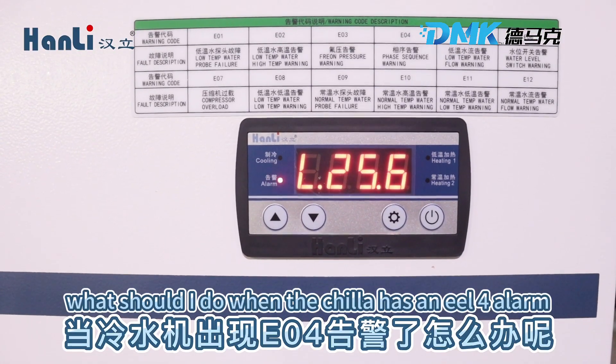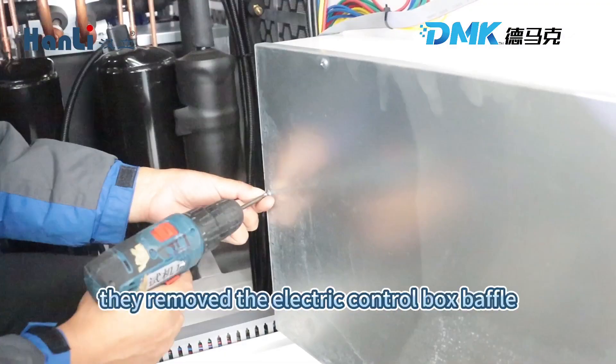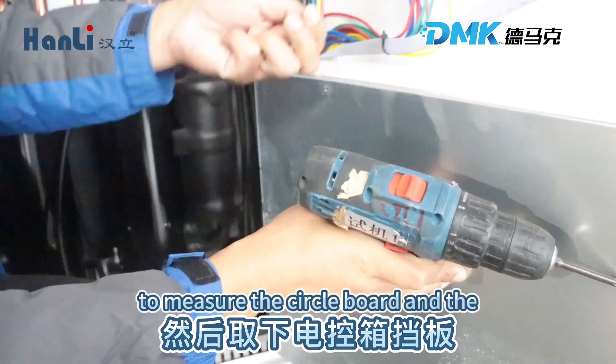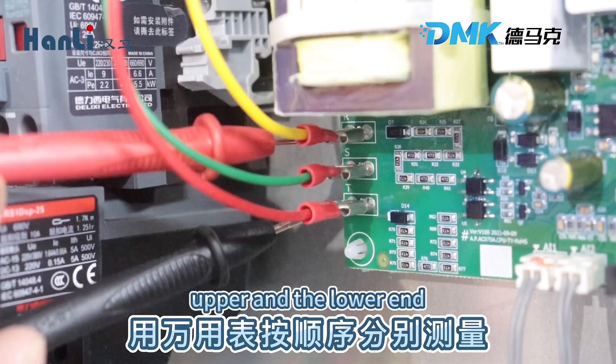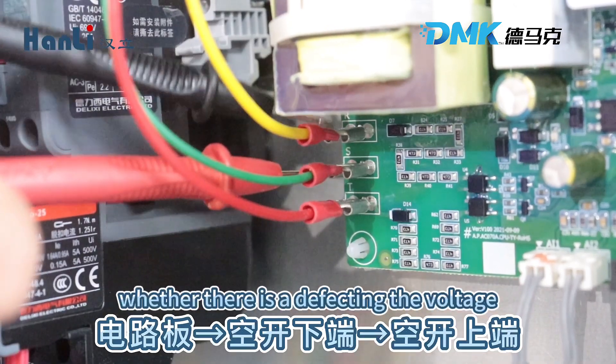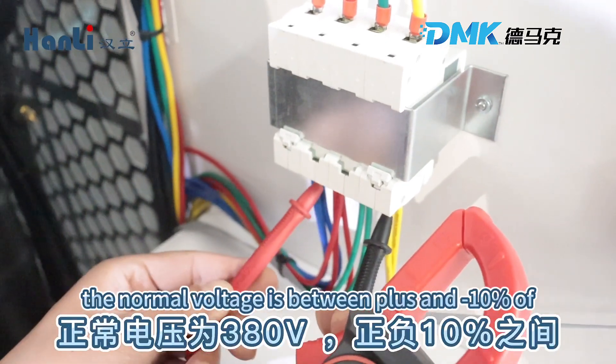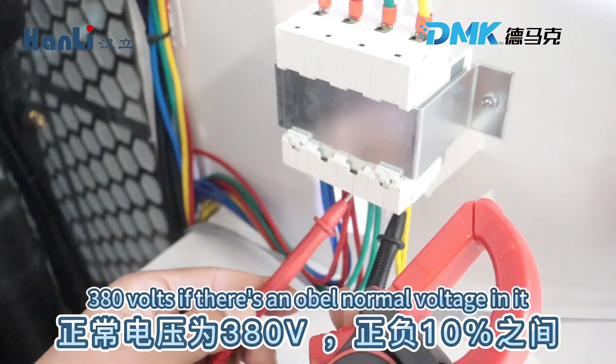What should I do when the chiller has an E04 alarm? First, open the chiller baffle, then remove the electrical control box baffle. Use a multimeter to measure the circuit board and the upper and lower end terminals in sequence, checking whether there is a voltage defect between two of the three live wires. The normal voltage is between plus and minus 10% of 380 volts.